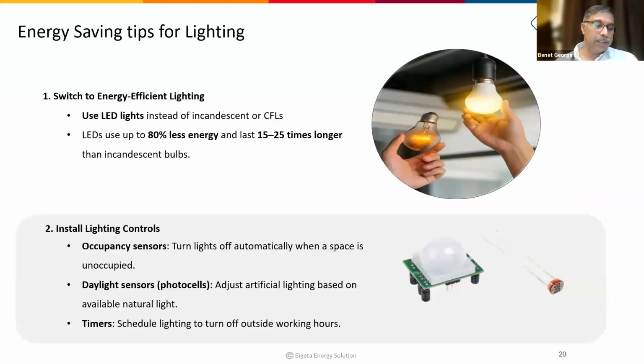So these are some of the savings opportunities. We can use LED lights instead of incandescent or fluorescent lamps, which consume 80% less energy. One more thing we have to remember is that light also produces heat, and if it is an air conditioned space, this heat will increase the energy consumption of the air conditioner. So by reducing the energy of the lamps, you are going to reduce the energy consumption of air conditioners also. So we have a double advantage. Then installing occupancy sensors, which will help to turn off lights automatically when the space is unoccupied. Daylight sensors and timers all will help to reduce the energy consumption.